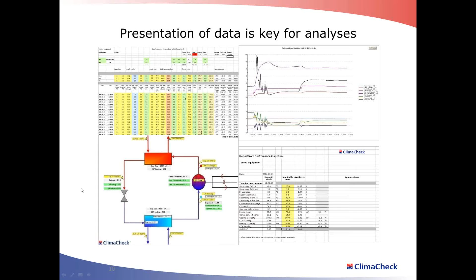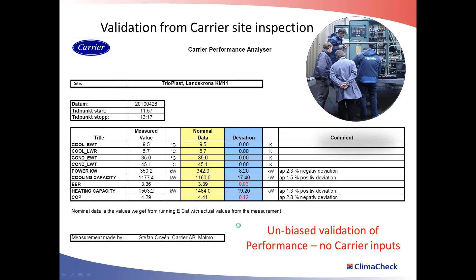This is an example from one of our customers, Carrier in Europe, where they measure the performance with ClimaCheck, and then they enter the operating conditions, that means the water temperatures on this chiller, and their software gives the nominal data that the chiller is sold to produce. And you can see the deviations. In this case, they are very small. And the nice thing with this is that the performance that ClimaCheck calculates does not include any Carrier information whatsoever. It's just the thermodynamics and the first law of energy.